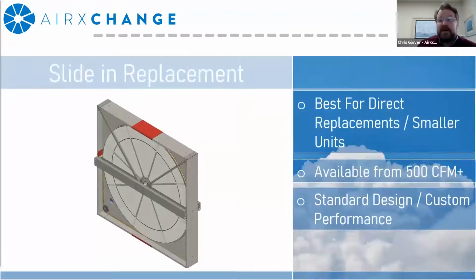Okay, for slide-in replacements, certain OEMs, I know Glenn mentioned Aaon's one of them, but there are others out there, develop cassettes into a track system where you can actually slide them in and out of the HVAC cabinet. So in certain cases, when you need a replacement or to service it, you can simply slide the old one out and slide a new one in, depending upon the manufacturer. Also, depending upon the manufacturer, you may need some additional blank-off panels, depending upon any dimensional differences between the new cassette and the old one. I will say, blank-off panels aren't fancy. They're just bent sheet metal, and they're just there to keep the air from bypassing around the cassette.